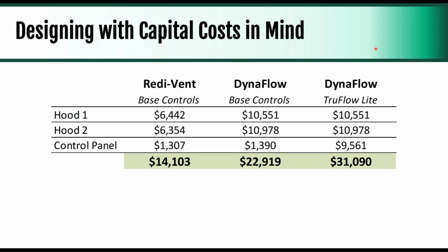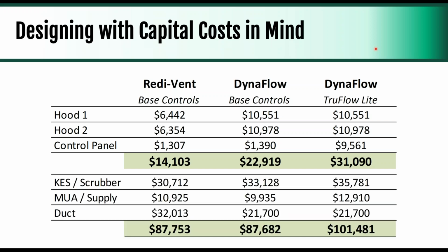Now when you talk about adding in the control panel for a high efficiency package with demand control, you're seeing a bigger increase. So this is where a lot of times you'll hear food service say, we can't afford demand control. It's ridiculously expensive. We don't want high efficiency hoods. Just give us the cheapest hoods you can get. Whereas on the engineering side, there's a lot of different inputs that you have to think about. So the size of the KES, pretty similar pricing here, just because we're using a cheaper version of the KES down here and a more full-featured one up here. And you've got VFDs up here, the makeup air, the supply air, same story, not too big of a difference.